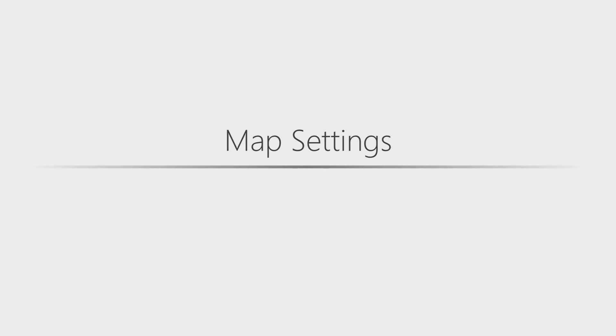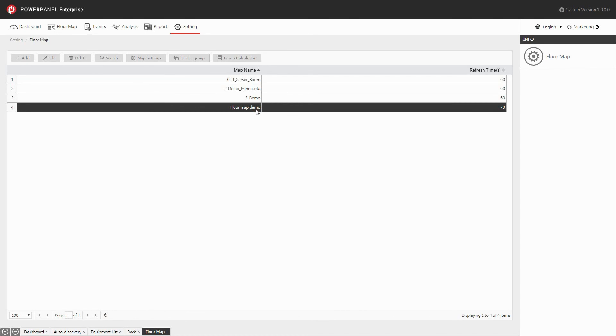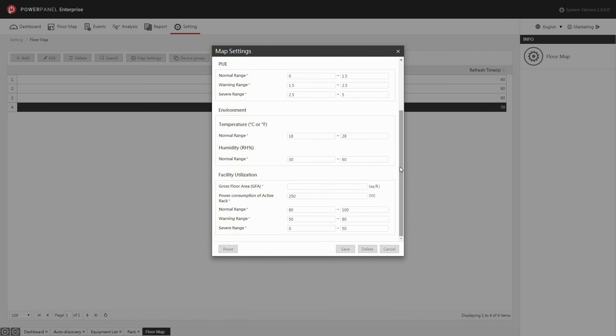The map settings allows you to manage the power capacity, PUE, environmental data, and facility utilization of the data center. In the floor map page, select the map that you would like to configure, then click map settings. Set the maximum power rating of the floor map, and then set the range of the output power values for normal, warning, and severe status. If needed, you can also change the default PUE, temperature, and humidity values according to your needs. Enter the total area of the floor map. You can also change the minimum power consumption of an active rack and the range of facility utilization values for normal, warning, and severe status if needed. Click save, and the map settings is complete.